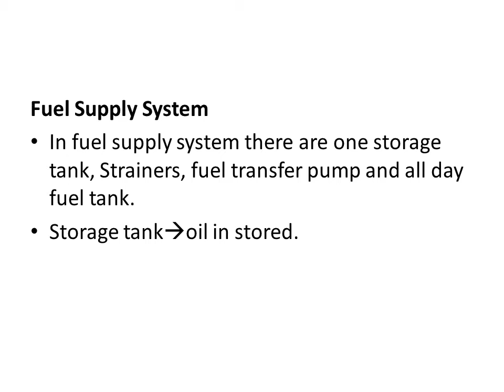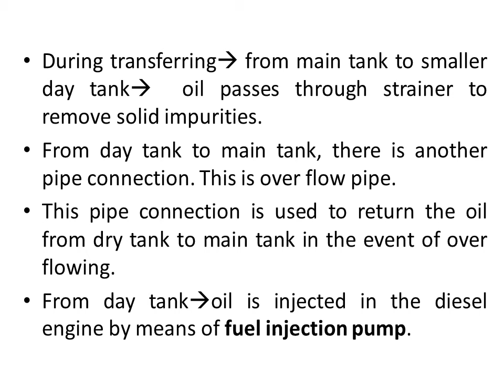First is the fuel supply system. It includes a storage tank and a fuel transfer pump, from which fuel is given to the diesel engine. The storage tank is where oil is stored before giving it to the engine. The oil in the main tank is shifted to a smaller day tank, passing through a strainer to remove solid impurities. There is a pipe connection, the overflow pipe, which returns oil from the day tank to the main tank in the event of overflowing. From the day tank, oil is injected into the diesel engine by means of a fuel injection pump.